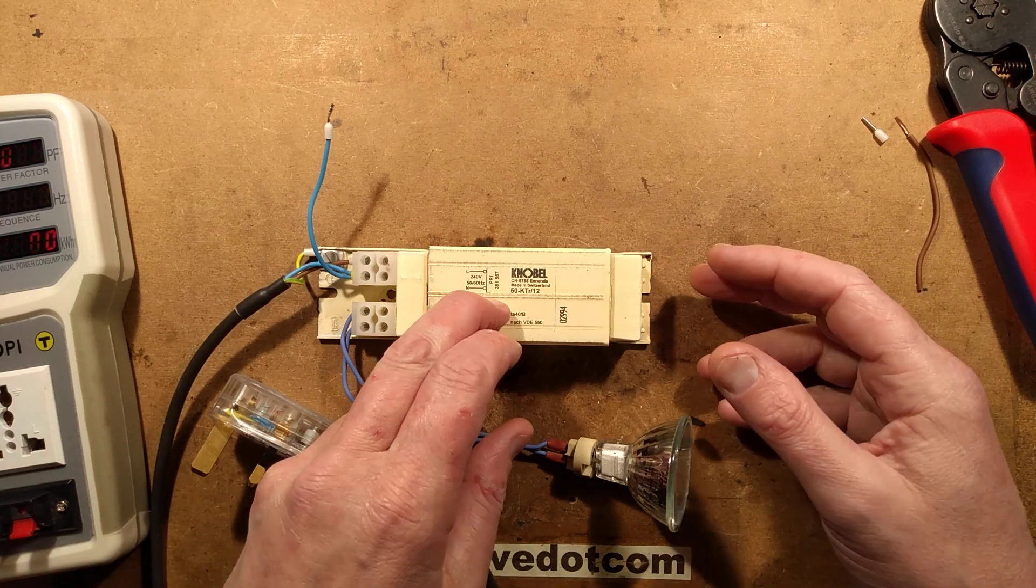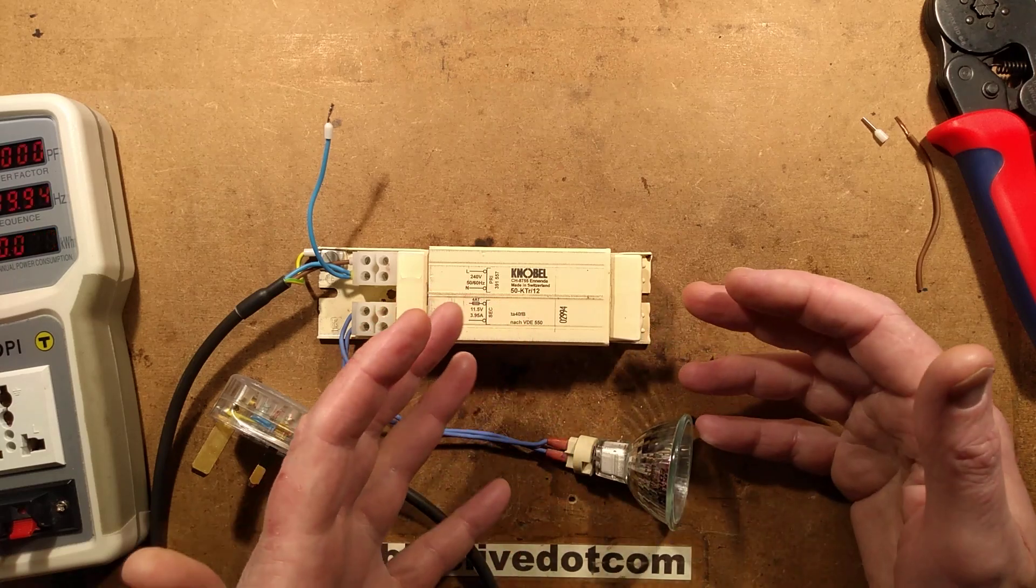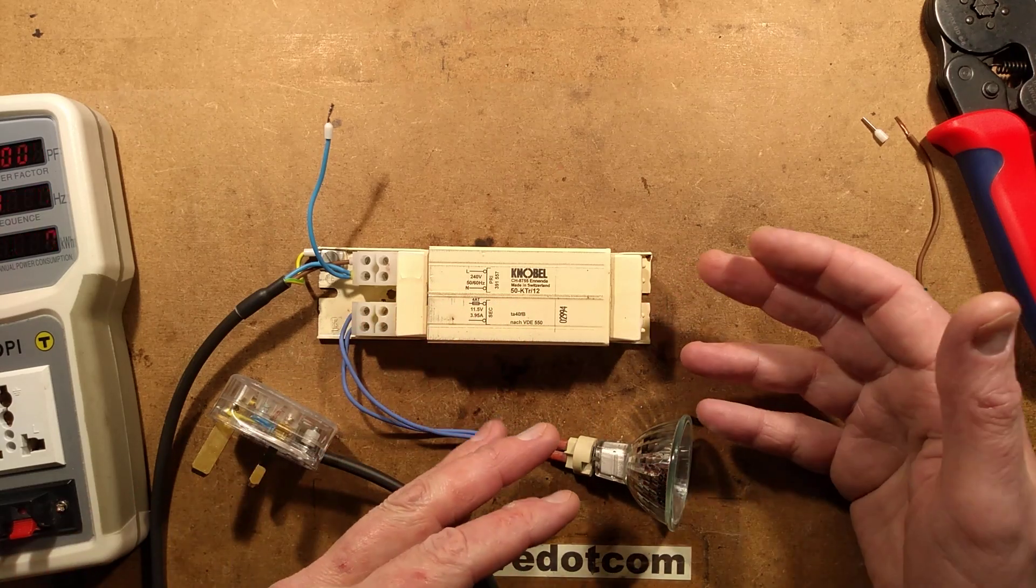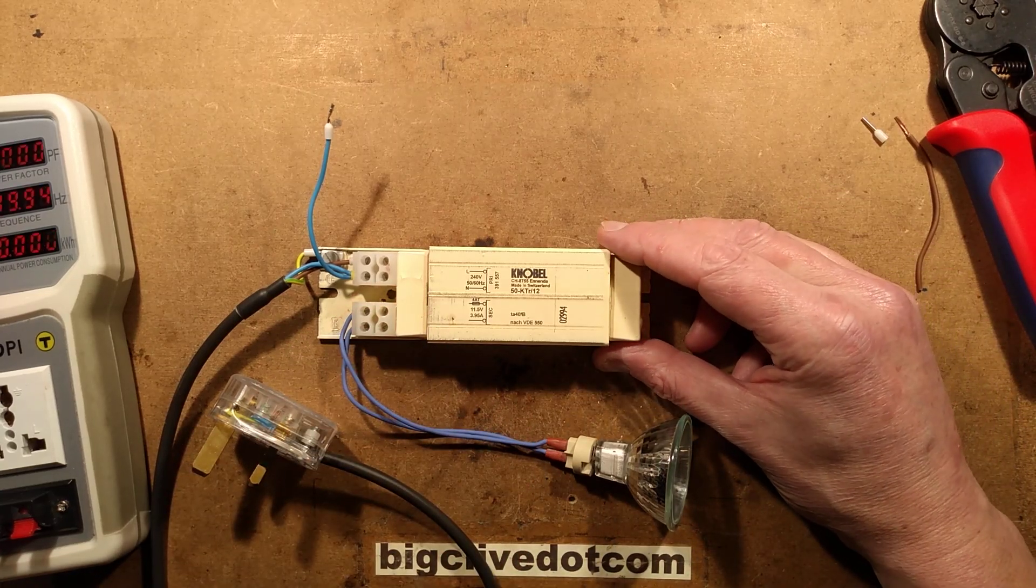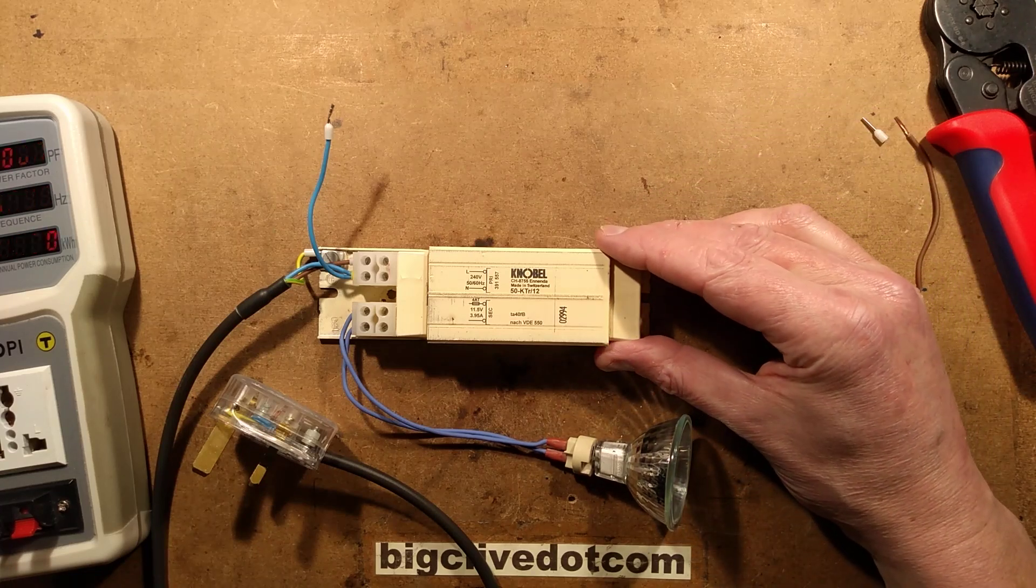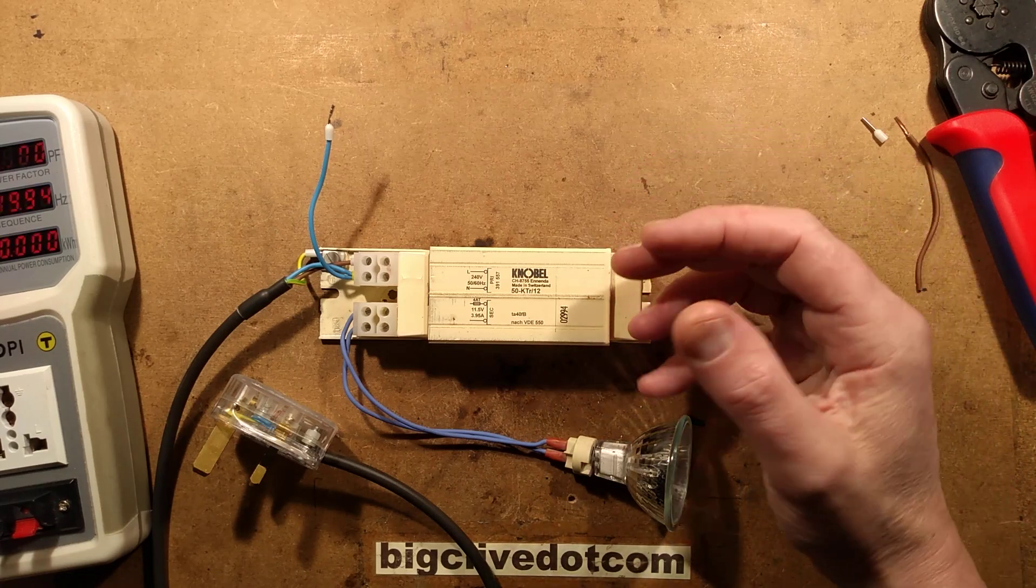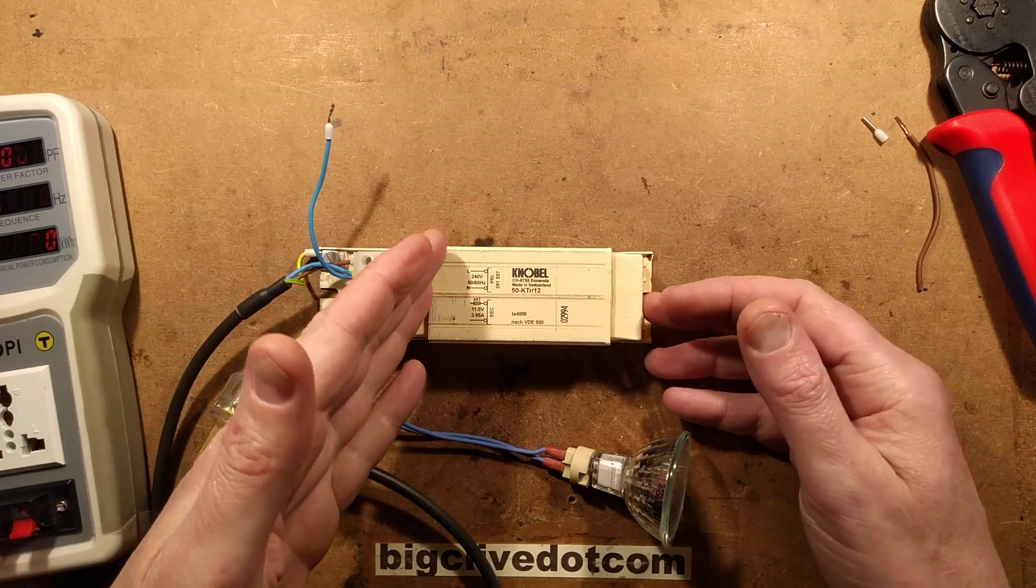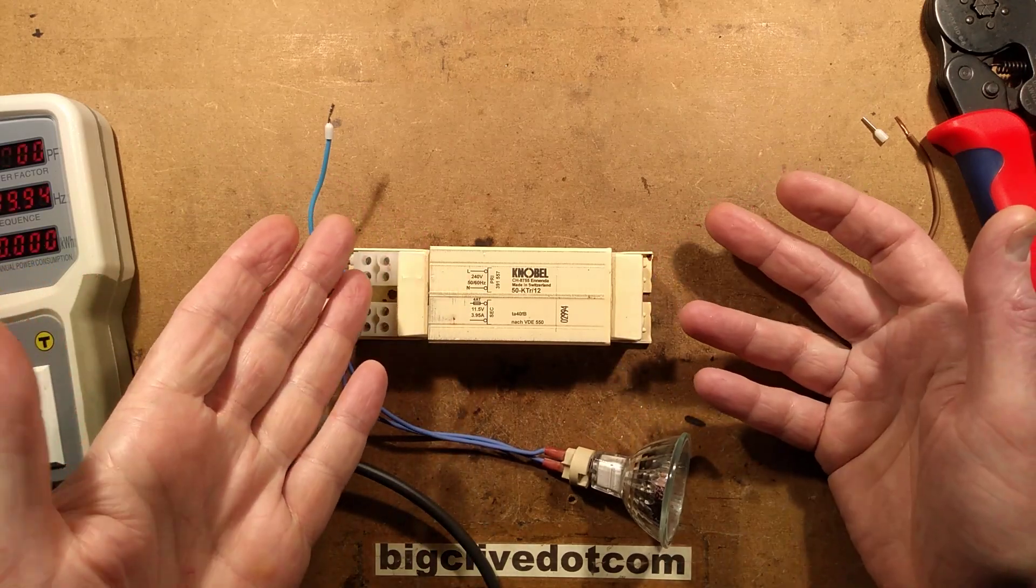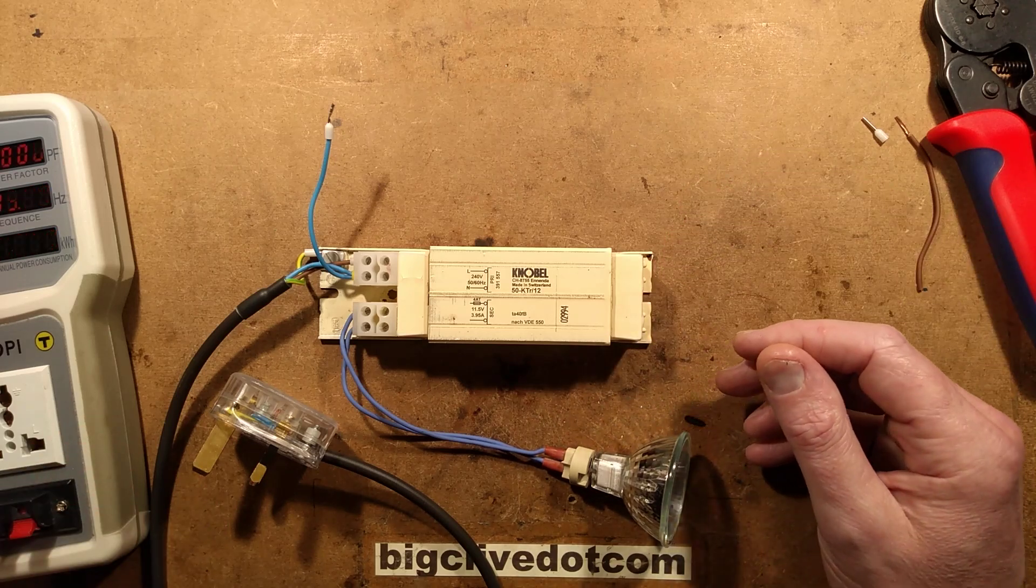Sometimes you get an appliance or an industrial machine that is just not happy with the local voltage. Either the voltage is too low for operation or it's too high and it causes it to overheat. This used to be a real common problem in British factories because occasionally we'd get 220 volt electrical equipment shipped that had clearly been pushed to the edge for 220 volts. And when you put it on a 240 volt supply, things like transformers and other equipment would start burning out on a regular basis. They just weren't happy because they were just being pushed that bit harder.